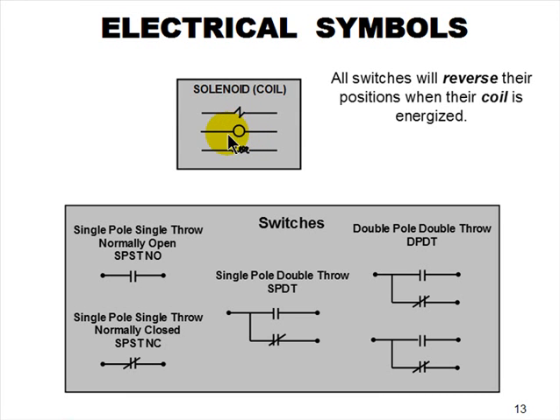Some manufacturers use this. When I see this on a set of plans, a complicated schematic for a unit, I'm thinking that's a motor, that's a load. Well, a solenoid is a load, but I just don't like motors looking like coils. Some manufacturers actually use the squiggle, and that's my best interpretation of that. It looks like the winding that it truly is.